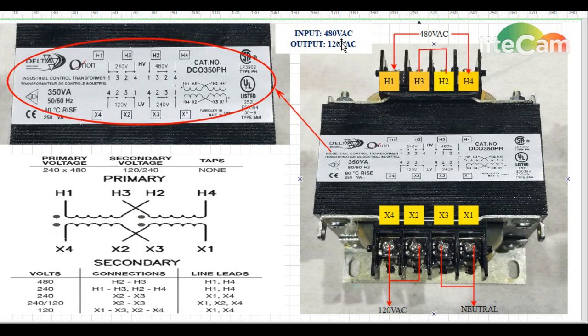As I mentioned earlier, we will be wiring this transformer to the 480 voltage, so we will be going with this pattern over here. You can see terminals 3 and 2 are jumpered together. 3 means H3, 2 means H2. That means we will be putting a wire on the terminal H3 and joining it to H2. Now we will be feeding a 480 to our terminal number 1, that is H1, and terminal number 4, that is H4. So we will be wiring according to this drawing over here.